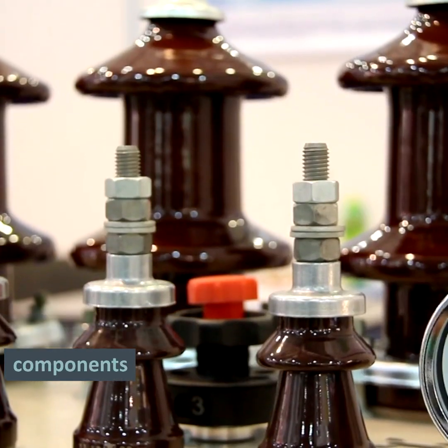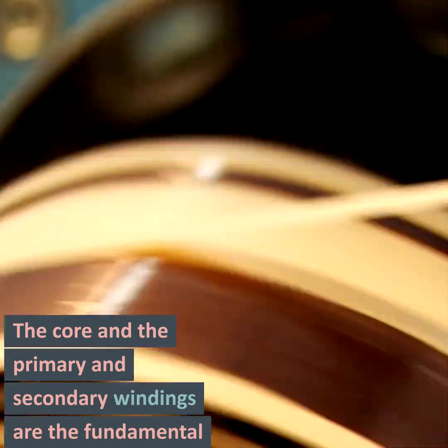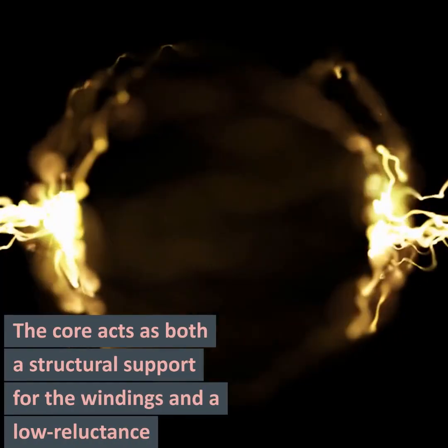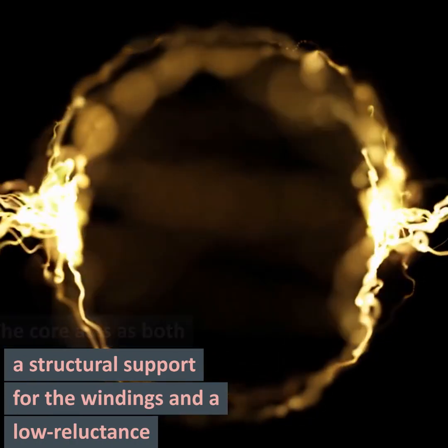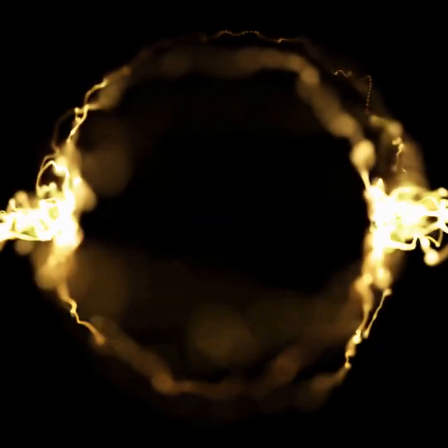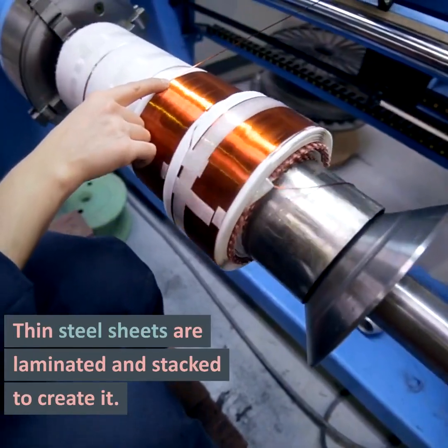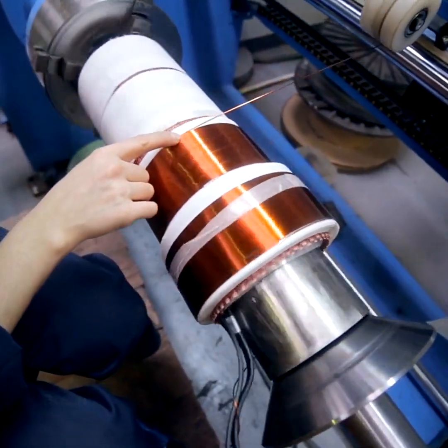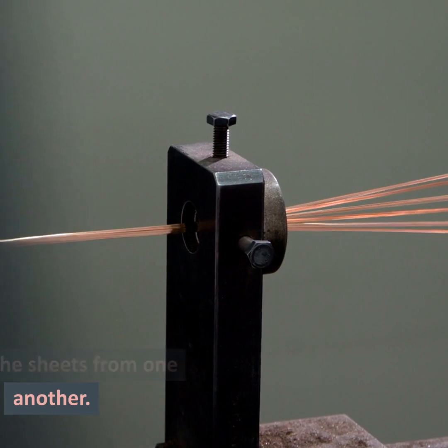Power transformer components. The core and the primary and secondary windings are the fundamental components of a transformer. The core acts as both a structural support for the windings and a low-reluctance channel for the magnetic flux. Thin steel sheets are laminated and stacked to create it. A covering separates the sheets from one another.